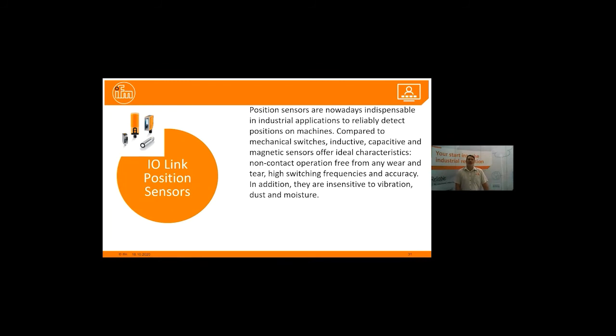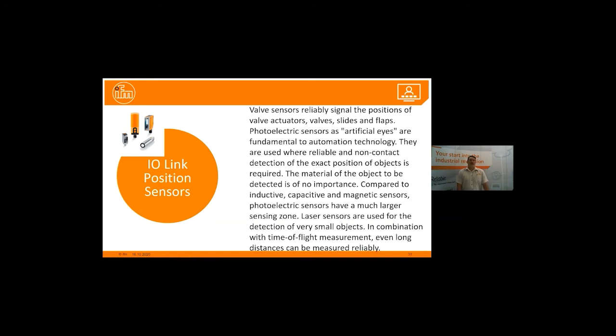Position sensors are nowadays indispensable in industrial applications to reliably detect positions on machines. Compared to mechanical switches, inductive, capacitive, and magnetic sensors offer ideal characteristics: non-contact operation, freedom from wear and tear, high switching frequency and accuracy. In addition, they are insensitive to vibration, dust, and moisture. Valve sensors reliably signal the position of the valve actuator. Valves, slides, flaps.